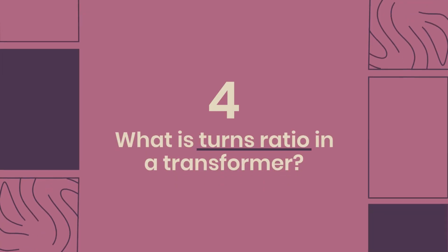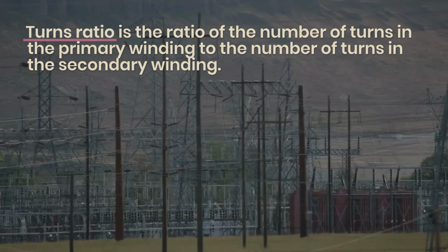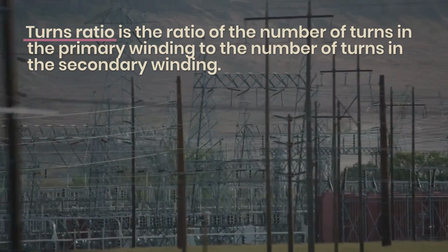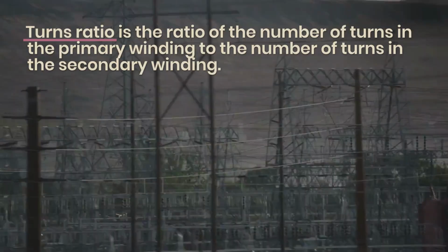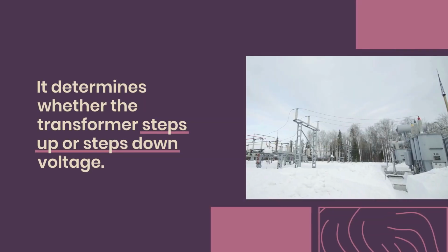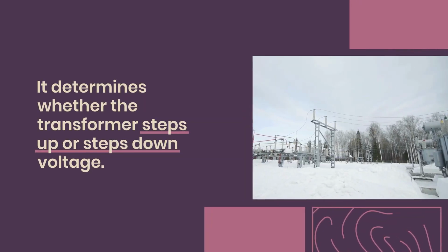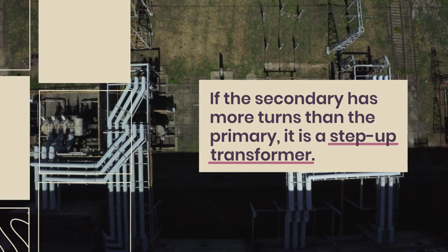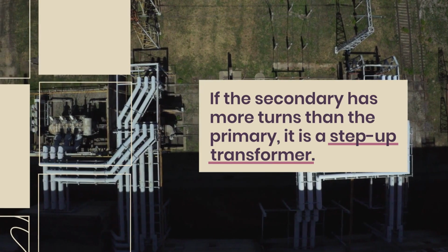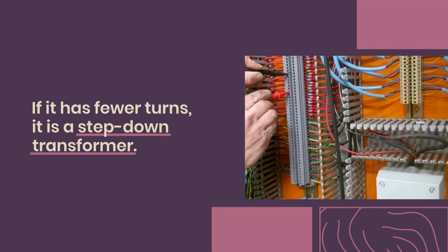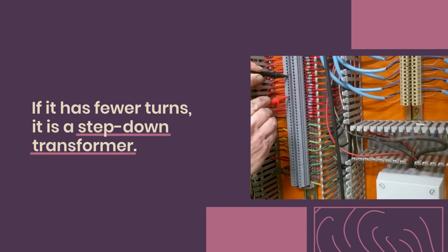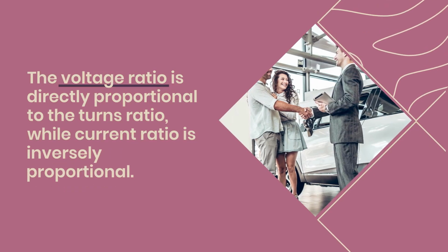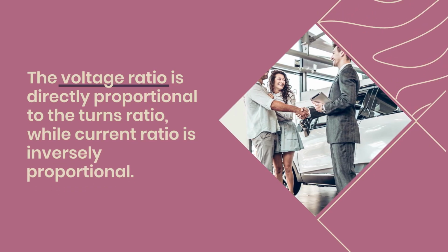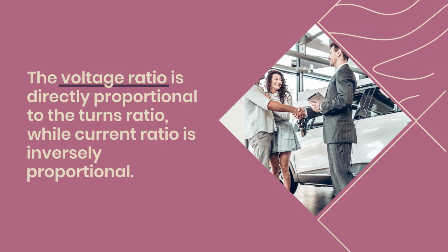4. What is turns ratio in a transformer? Turns ratio is the ratio of the number of turns in the primary winding to the number of turns in the secondary winding. It determines whether the transformer steps up or steps down voltage. If the secondary has more turns than the primary, it is a step-up transformer. If it has fewer turns, it is a step-down transformer. The voltage ratio is directly proportional to the turns ratio, while current ratio is inversely proportional.